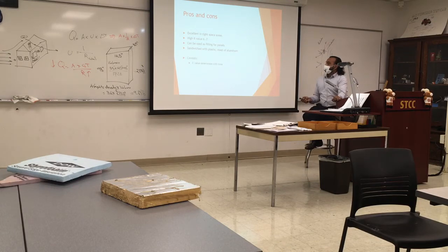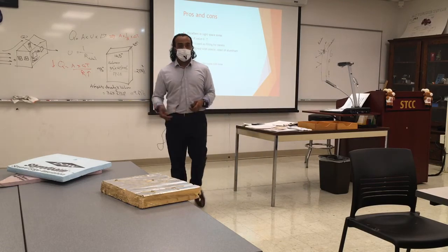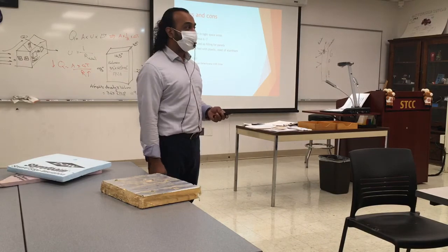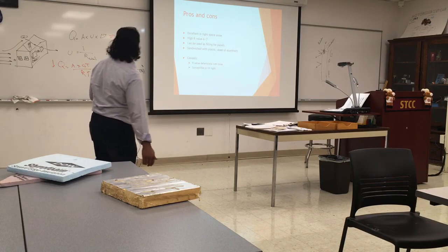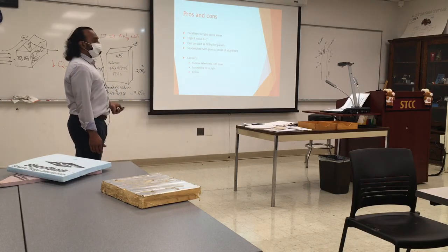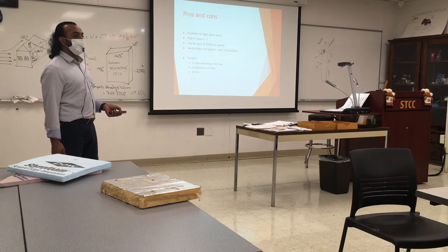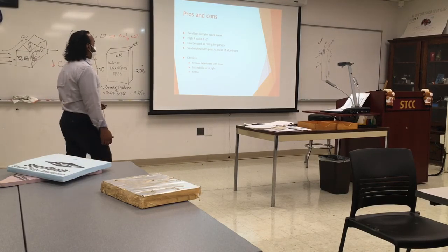Caveats or problems: R value deteriorates with time, depending on the brand and how much money you put on them. You can see two insulation panels from different brands, and one of them is much cheaper. They look the same, but some of them, with time, react with oxygen and deteriorate. They are susceptible to UV light, so they cannot be outside or in direct sunlight because eventually they will lose R value, and they're very brittle.